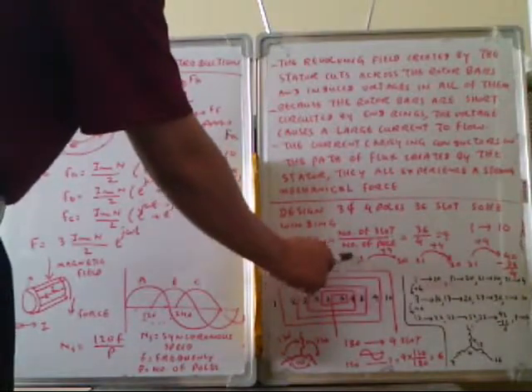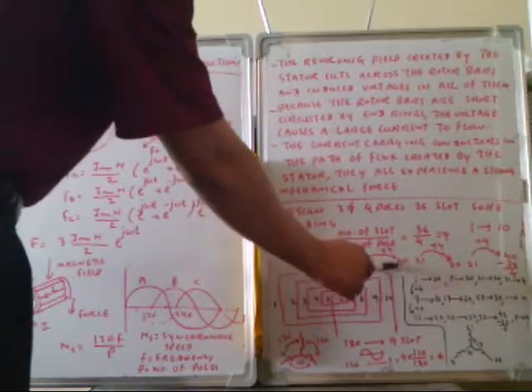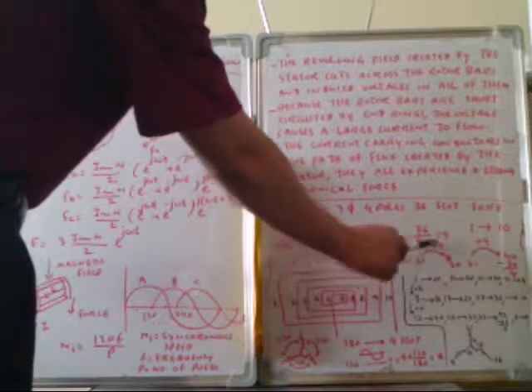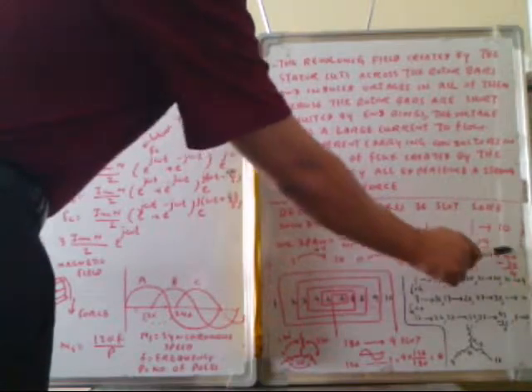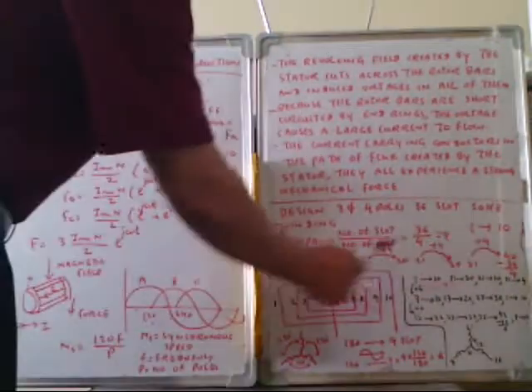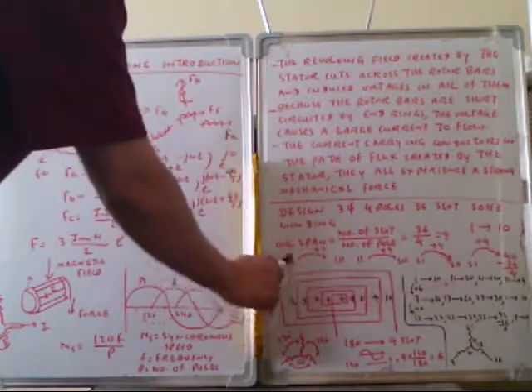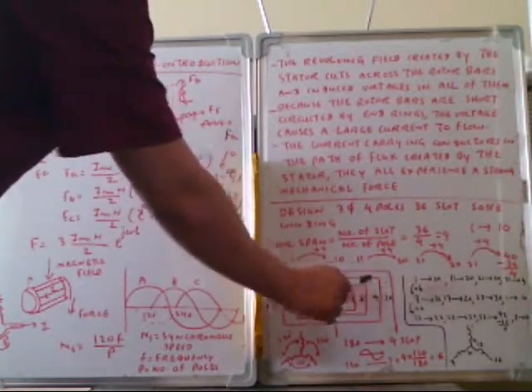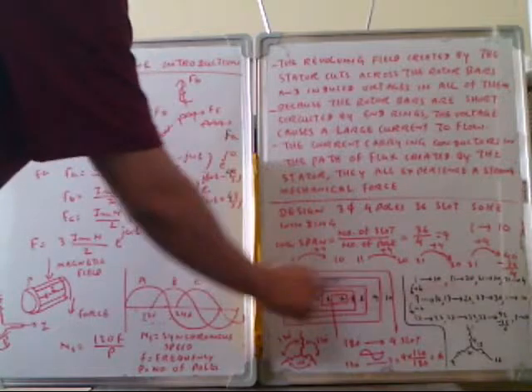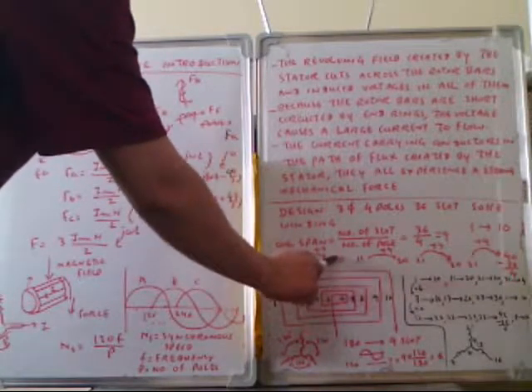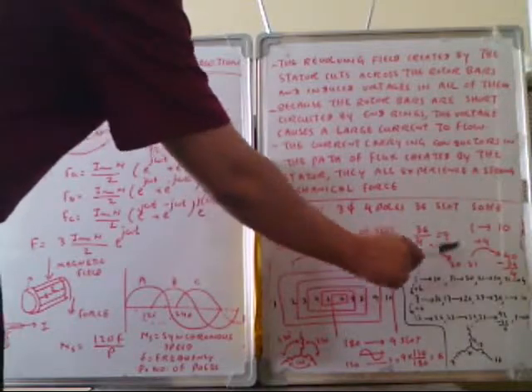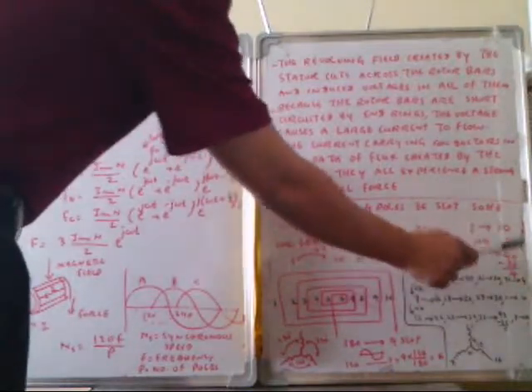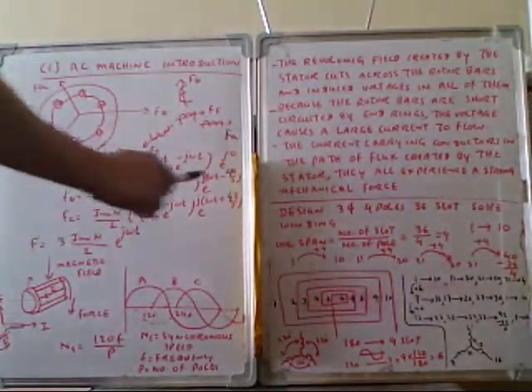This is the first pole. 11 plus 9 is 20, 21 plus 9 is 30, 31 plus 9 is 40. But we only have 36 slots, so we subtract 36 to get slot 4. We start from slot 1 to 10. This is the 3-phase construction: 1 to 10 for pole 1, 11 to 20 for pole 2, 21 to 30 for pole 3, and 31 to 4 for pole 4. So these 4 poles make one phase.